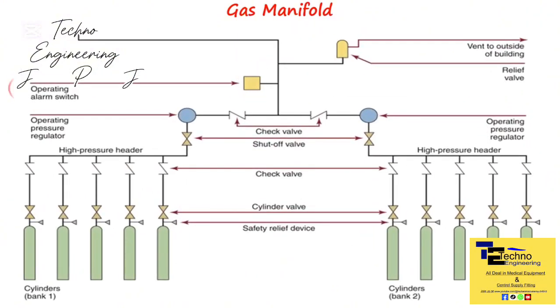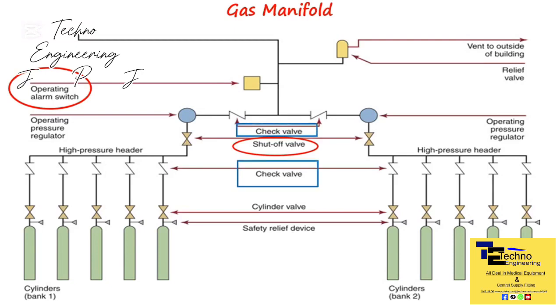The manifold is equipped with manual or automatic changeover systems between full and empty banks, and a low-pressure alarm signals when it's time to switch cylinders or the manifold rack, facilitated by a shut-off valve. Check valves ensure unidirectional gas flow through the manifold, while regulators maintain pressure at the working level. For added safety, a relief valve activates in case of regulator failure or high pressure, protecting the user's equipment from damage.